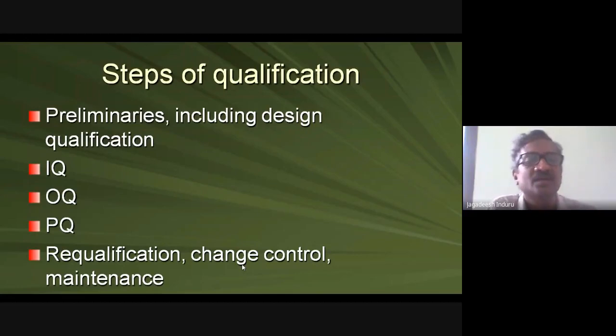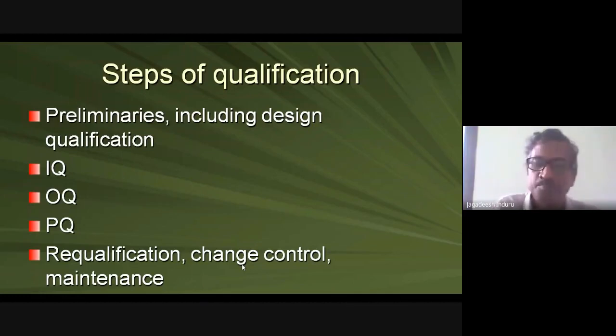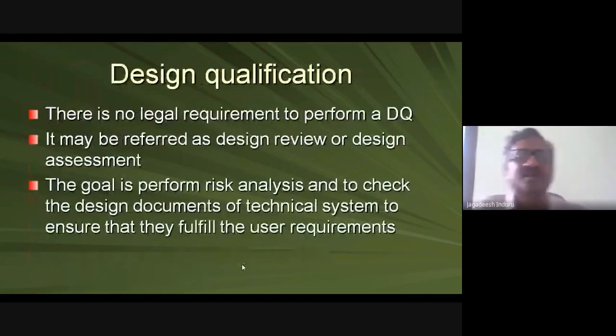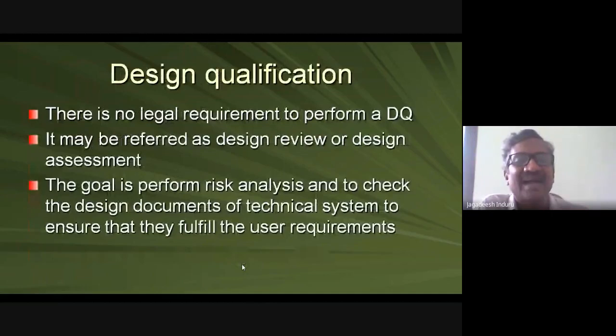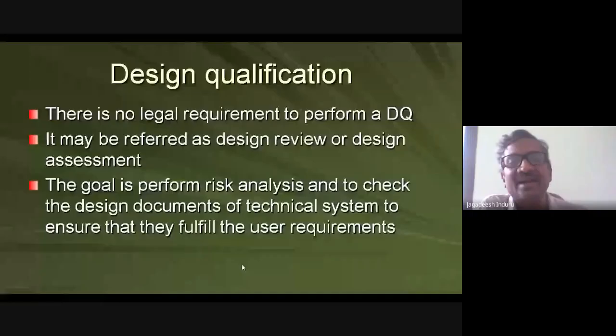DQ is the planned stage done once in a lifetime. First you do IQ, OQ, PQ, then change control for qualification maintenance throughout the equipment's lifetime. Preliminaries and Design Qualification are done only once, before purchasing equipment. In the DQ there is no mandatory legal document because it is an idea and charting-out stage, so it may not be required by guidelines.